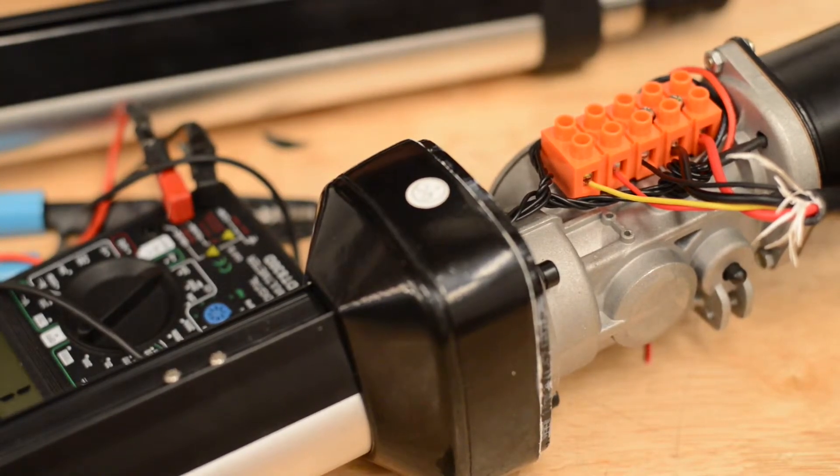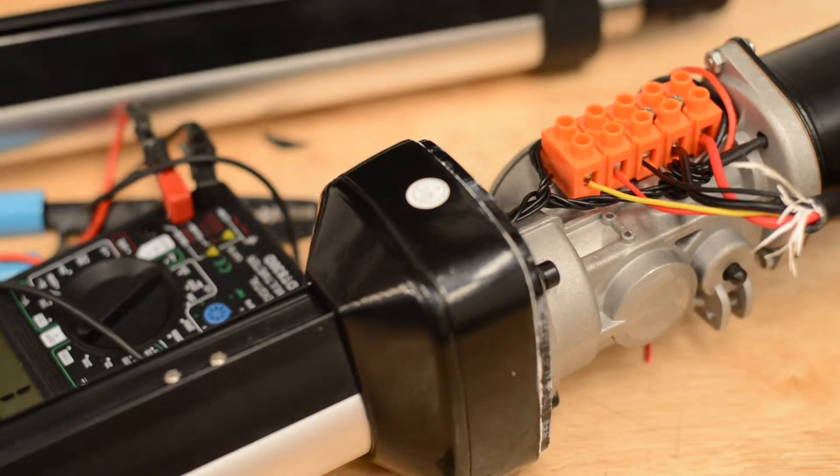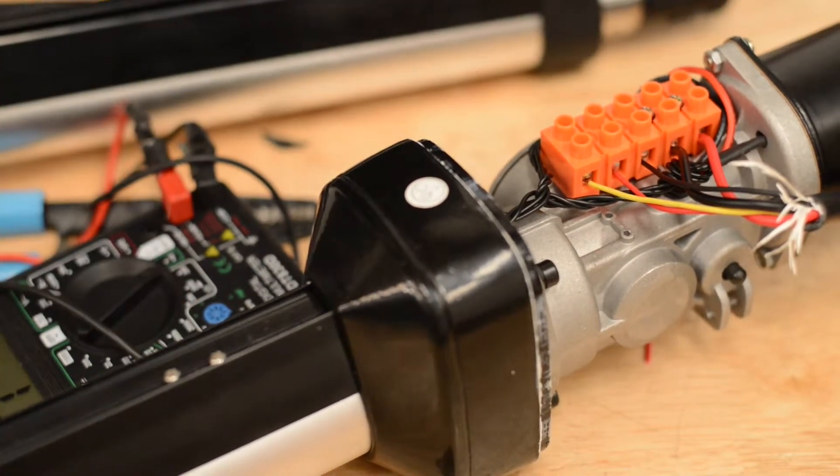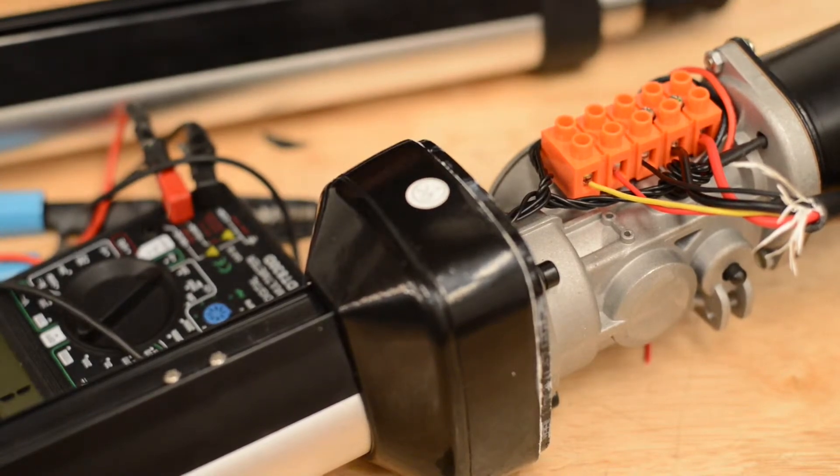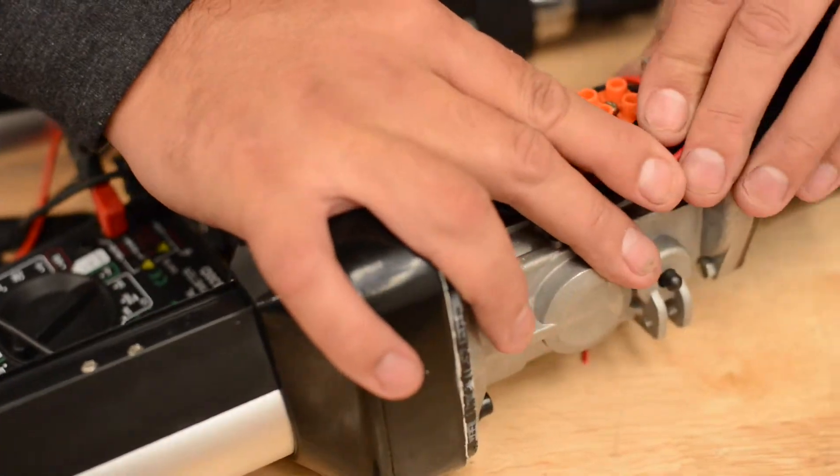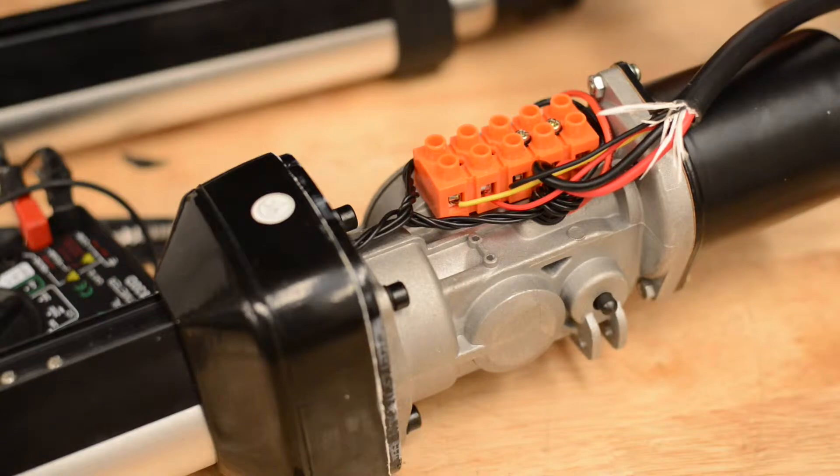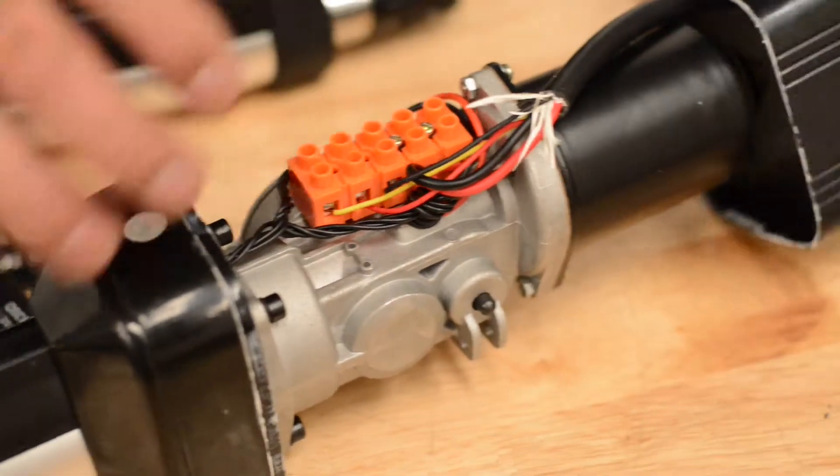So we're going to assume everything's fixed because we got continuity. We checked it on this end of the wire. So we know the wire is good. We know the limit switch is good. So now we can put it back together, confident that we have everything connected properly. When we're putting it back together, the more narrow side goes on the bottom.